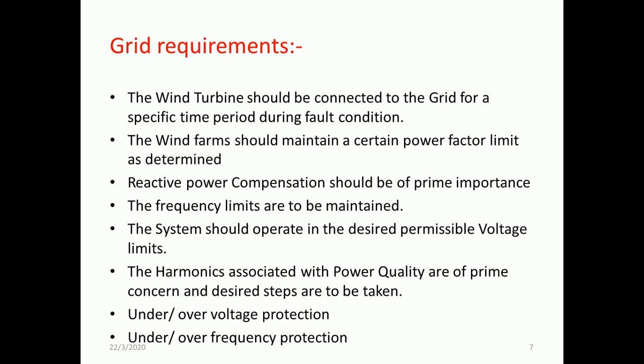The system should operate within the permissible voltage limits depending upon the voltage level, which we will be discussing in the further slides. The harmonics associated with power quality are of prime concern, and steps should be taken, like the design of harmonic filters and minimum use of electronic devices. There are various measures which can be used to reduce the harmonic content in the system. Again, a proper protection scheme in terms of under and over voltage protection should be employed. Further, a frequency protection unit should be employed to maintain the frequency within permissible limits.